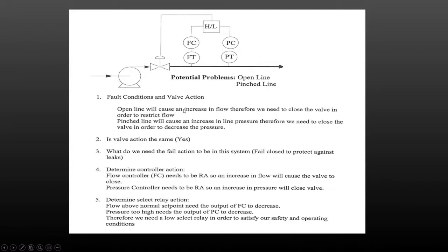An open line is going to cause an increase in flow; therefore we need to close the valve to restrict the flow. A pinch line will cause an increase in line pressure; therefore we need to close the valve to decrease the pressure. Close the valve in both cases — are the valve actions the same? Yes. So the fail action needed is fail closed, in order to protect against leaks.